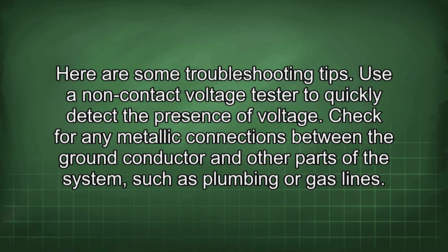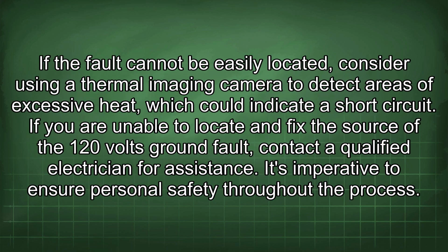Here are some troubleshooting tips. Use a non-contact voltage tester to quickly detect the presence of voltage. Check for any metallic connections between the ground conductor and other parts of the system, such as plumbing or gas lines. If the fault cannot be easily located, consider using a thermal imaging camera to detect areas of excessive heat, which could indicate a short circuit. If you are unable to locate and fix the source of the 120 volts ground fault, contact a qualified electrician for assistance. It's imperative to ensure personal safety throughout the process.